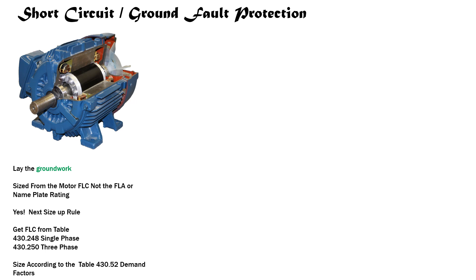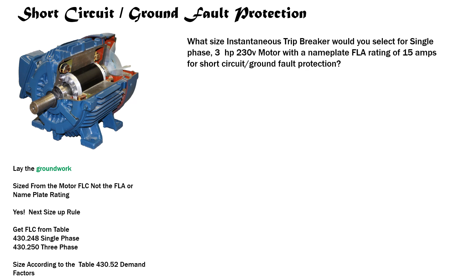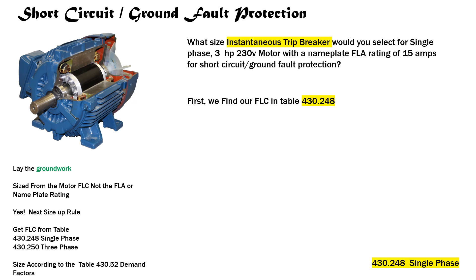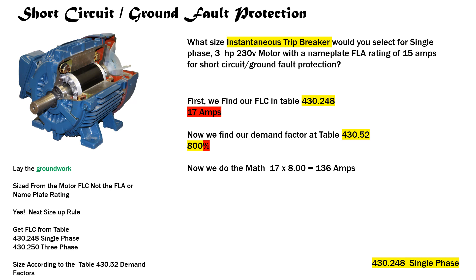I threw this one in for a little bit of fun — hang with me on this one. What size instantaneous trip breaker would you select for a single-phase, three horsepower, 230 volt motor with a nameplate FLA rating of 15 amps for short circuit ground fault protection? It's single-phase, three horsepower, 230 volt, and an instantaneous trip breaker. We find our FLC in table 430.248 — it's 17 amps. We head to table 430.52, and this is where it gets fun: the demand factor is 800 percent.